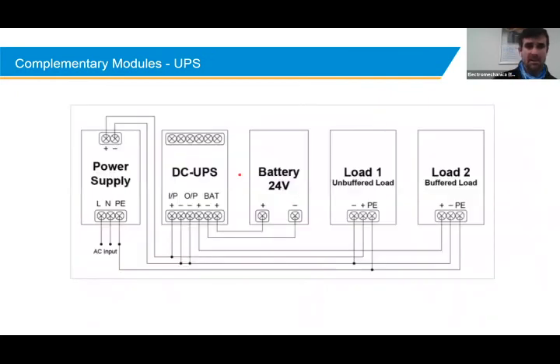Just having a look at the diagram for wiring such a UPS into the system. So you've got your standard Delta power supply feeding into the input of the UPS. The output of the UPS will go to your buffered load, and an unbuffered load, one that would switch off if there's a power failure, can be connected directly to the power supply itself. The battery is a 24 volt battery, 15 amp hour, 30 amp hour. The bigger the amp hour battery you go for, the longer it's going to take to charge it up. That's about all. So this is a great little design for a basic UPS and a PLC control system.